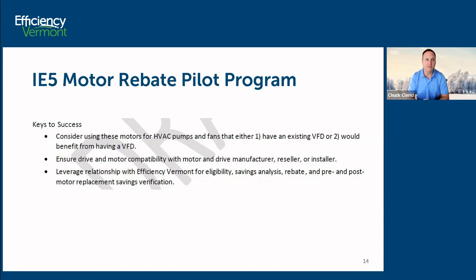But if the drive is 10 years old or older, and it's still working, but it won't work with the new motor, we probably have a justifiable end of life discussion. There are very forward thinking customers who say, listen, it's been 10 years, my drives have been operating, I know they're nearing their end of life, I cannot afford for them to go down, so I'm going to proactively replace them. And if that replacement ends up becoming a motor and a drive to gain efficiency on both, then I think we have a clear path to support the motor and the drive.